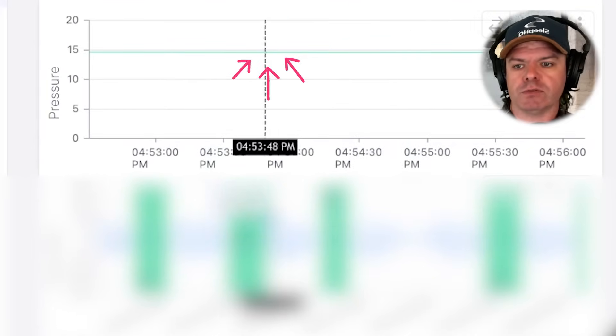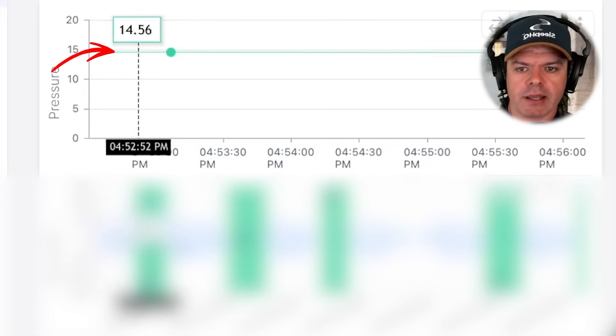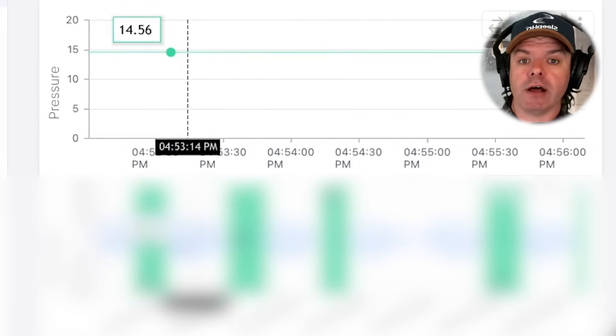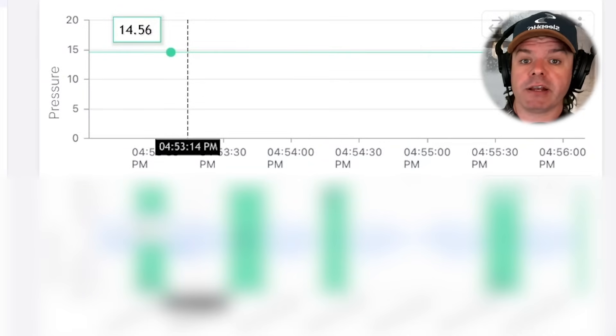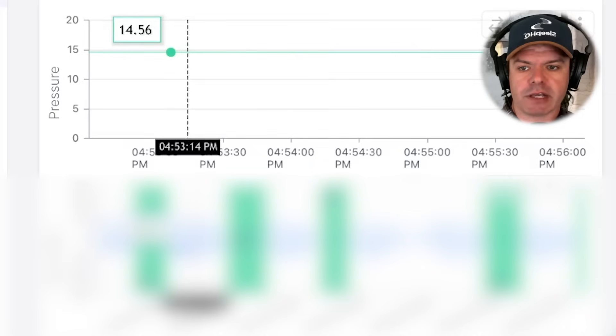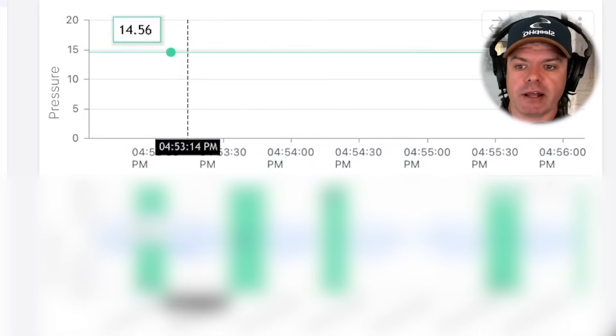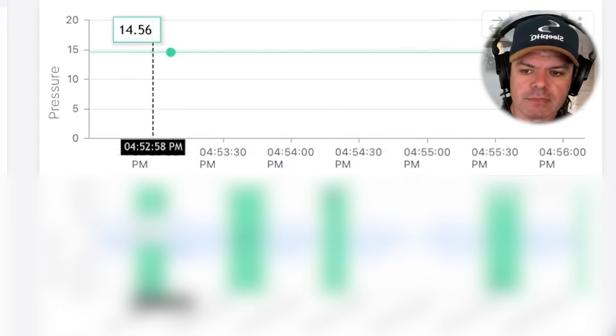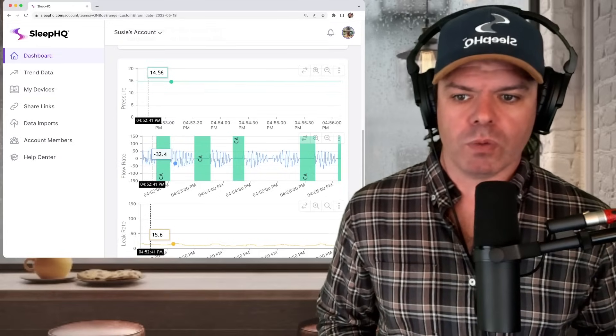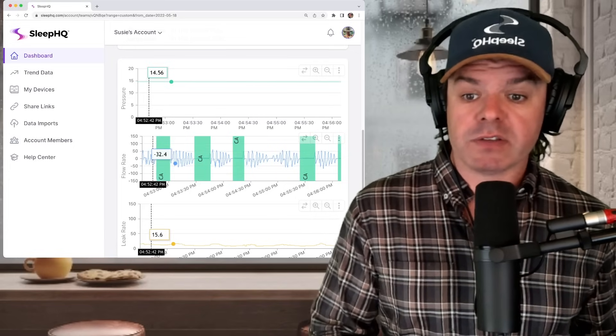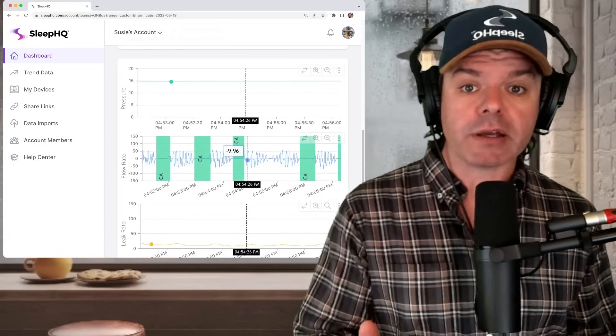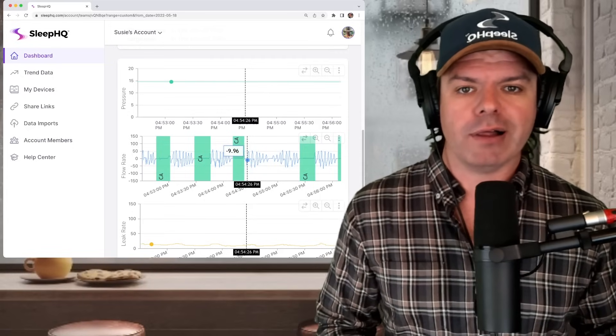Now just above the flow rate, the breathing is the therapy pressure levels. You can see this green line here. And what you can see is that it's very stable, even though this device is an automatic BiPAP machine that will vary the pressure automatically. You can see right here, it's behaving more like a CPAP machine at one fixed level of pressure. And you might be asking yourself, why is it doing that? Because we've got all these events. Shouldn't the machine be responding to the apnea, increasing the pressure?